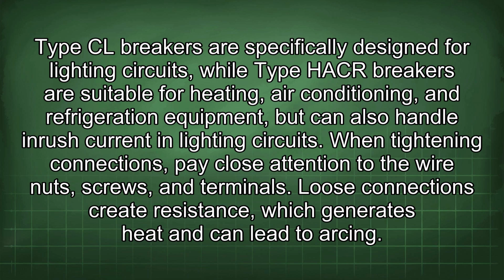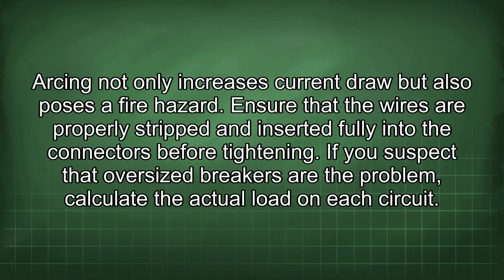When tightening connections, pay close attention to the wire nuts, screws, and terminals. Loose connections create resistance, which generates heat and can lead to arcing. Arcing not only increases current draw but also poses a fire hazard. Ensure that the wires are properly stripped and inserted fully into the connectors before tightening.